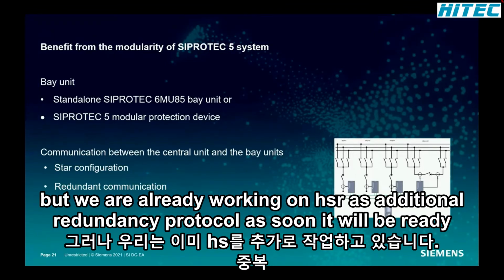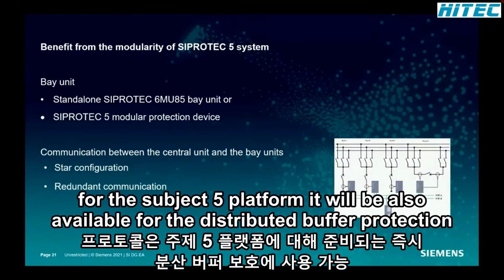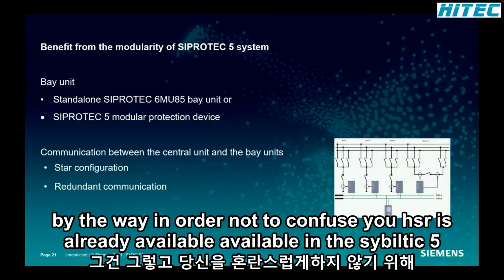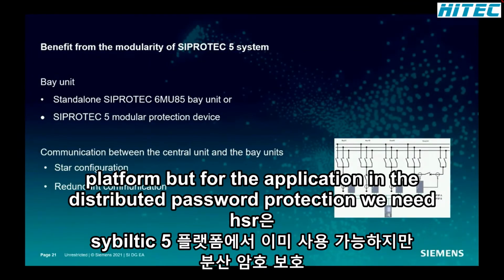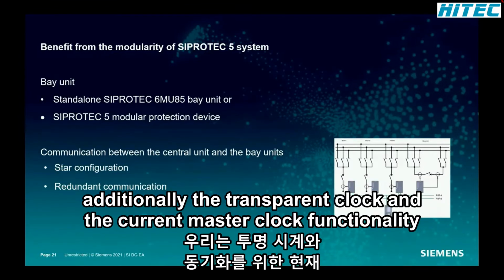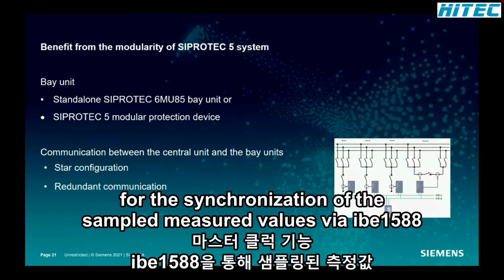As soon as it is ready for the SIPROTEC 5 platform, it will also be available for the distributed busbar protection. By the way, in order not to confuse you, HSR is already available in the SIPROTEC 5 platform. But for the application in the distributed busbar protection, we additionally need the transparent clock and the current master clock functionality for the synchronization of the sampled measured values via IEEE 1588.